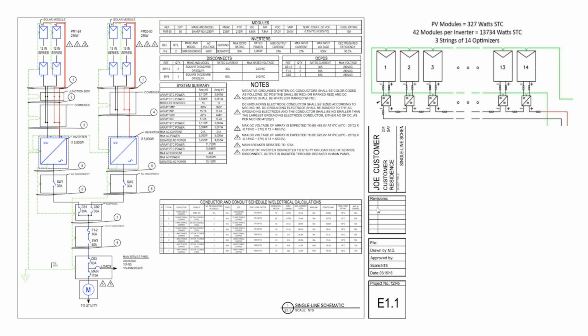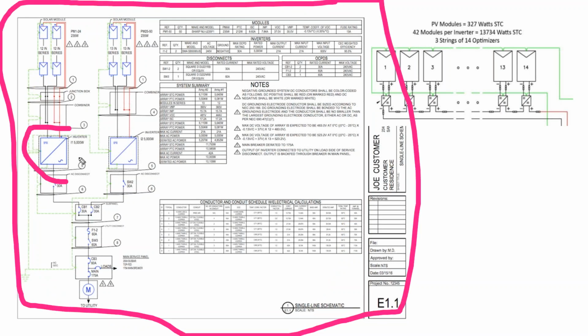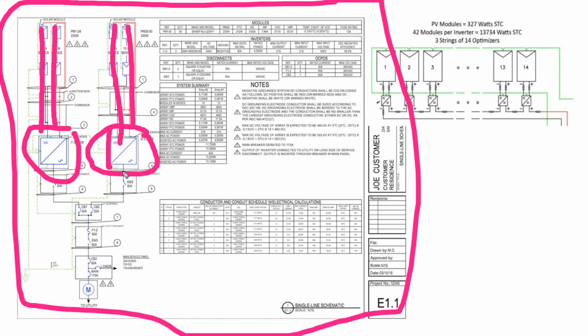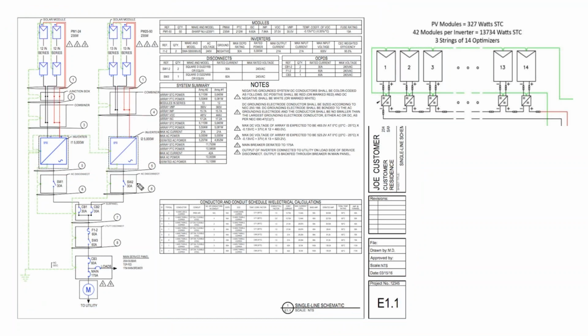If you're using string inverters or DC optimizers, the design is a little more complicated. This kind of document I don't hand draw—I use computer software, and we have a design-your-solar-roof class that focuses more on the design aspect. What I can see from this document is that this one-line diagram is for two string inverters. I call them string inverters because we have traditional circuits of solar panels wired directly into the inverter box, with various disconnect switches and other hardware.